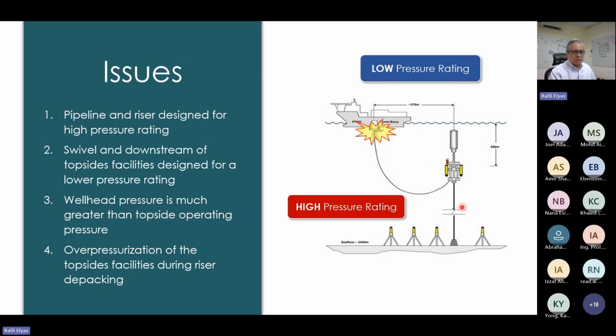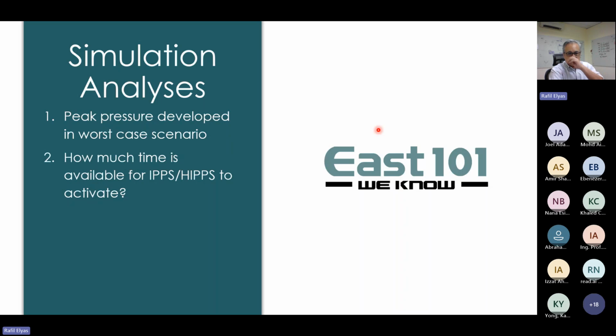and you restart the compressor, as you restart your facility, sometimes what happens is within this riser, when you shut down, all the liquids will go to the lower points, and you'll find a gas-packed riser. This gas-packed riser will be at a high pressure. When you start up your system, or if you open your valves over here, you might get a sudden overpressure during when this riser starts to depack. So this computation is a bit more straightforward. We take a look at the peak pressure developed in the worst case scenario.